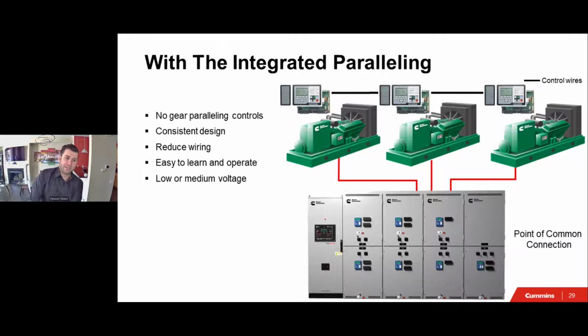And obviously this would be easier to learn and operate, and it can be used on both low voltage and medium voltage. A lot of times I get asked, well, what about medium voltage? It's the same. The control is the same. It doesn't care if this is a 4160, 23,000 volts, or 480, or 600.